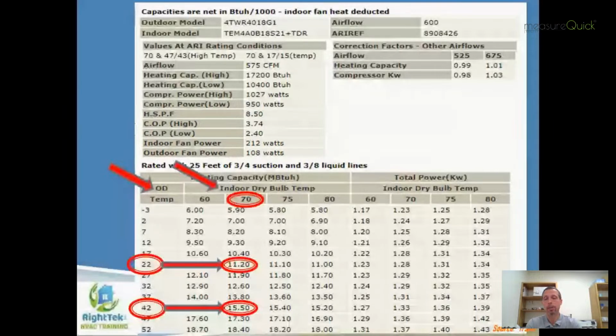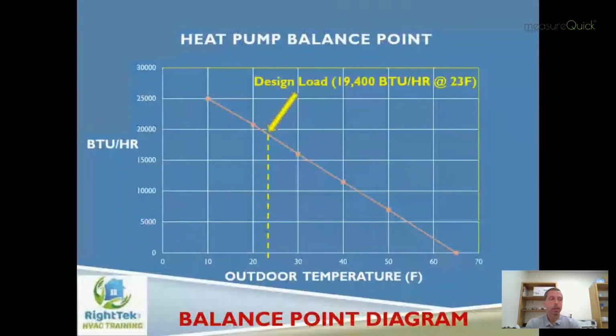So where am I going to go with this information? What I always advocate is to create what we call a thermal balance point diagram. So just a simple piece of graph paper, and you see across the bottom, I've got outdoor temperature decreasing as you go from right to left. And then going up the left-hand side, you'll see we've got BTUs per hour.